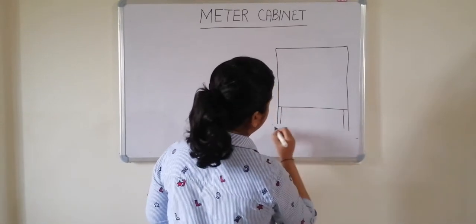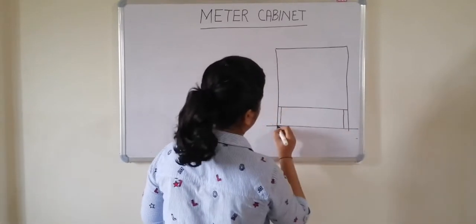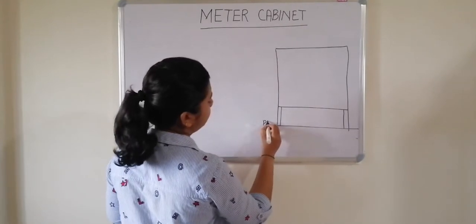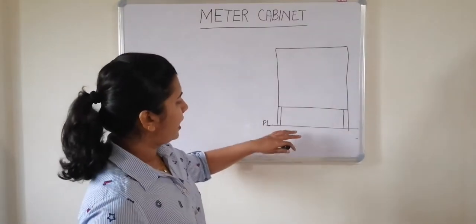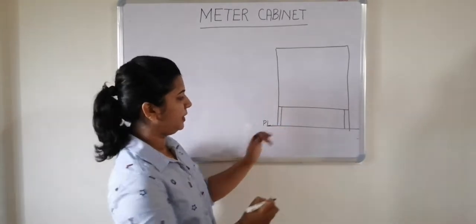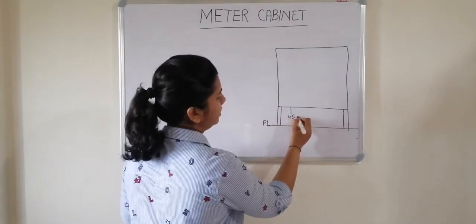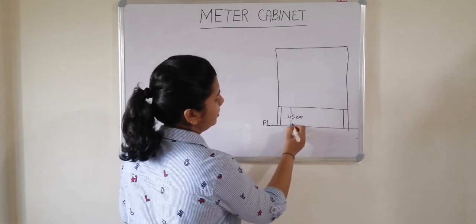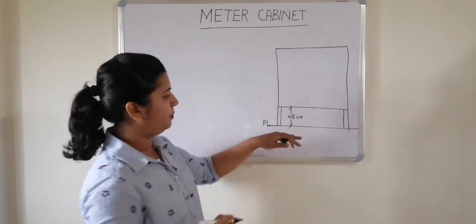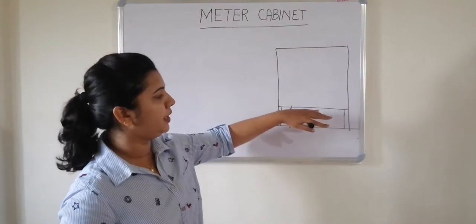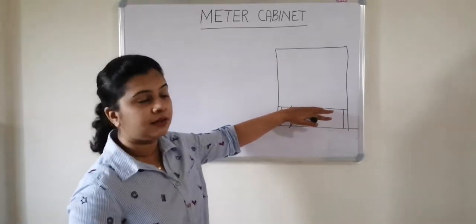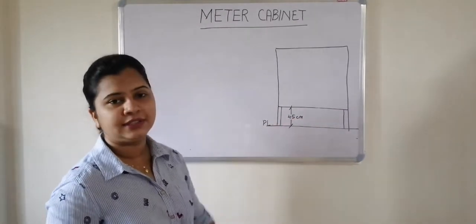This is the stand of it, and this is your plinth level. Now the height of meter panel from this plane should be not less than 45 centimeter. The minimum height from the plinth level or the ground level to your meter panel should be 45 centimeter.